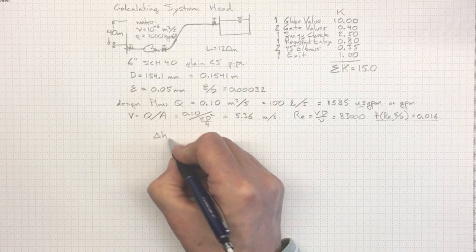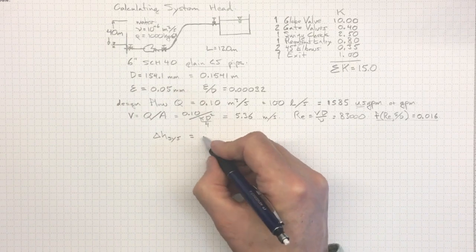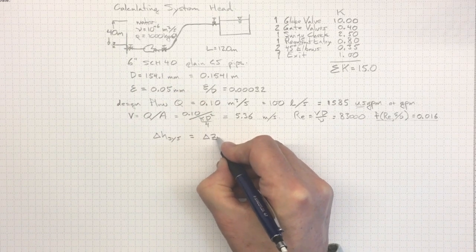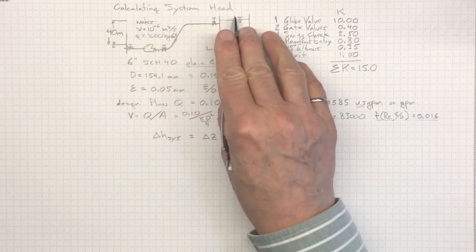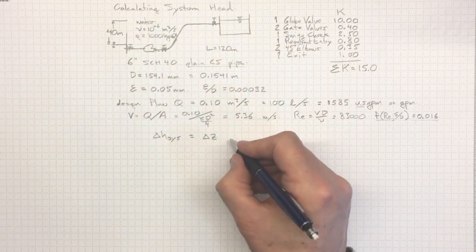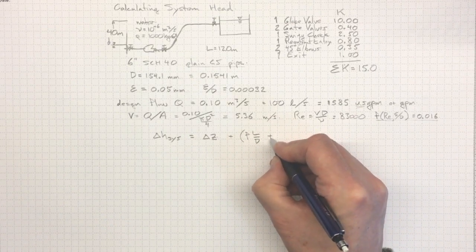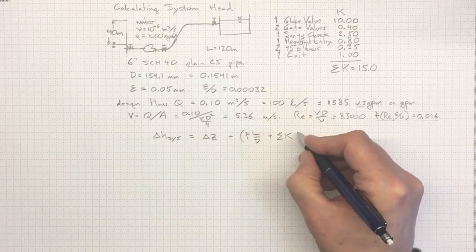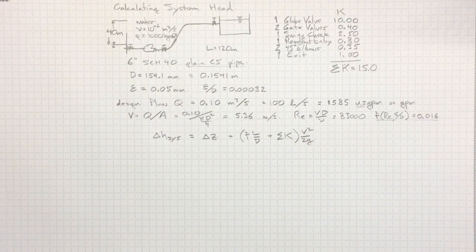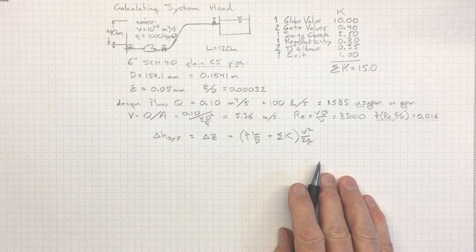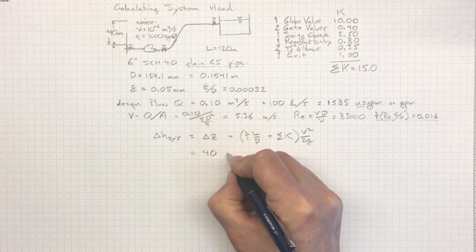So, the delta H for the system, as we saw before, it's going to depend on delta Z. There would be delta P, except in this case we've got atmospheric pressure at both these surfaces, plus F L over D, plus sigma K, all times V squared over 2G. And this is how we would have tackled the problem in the section purely on piping.